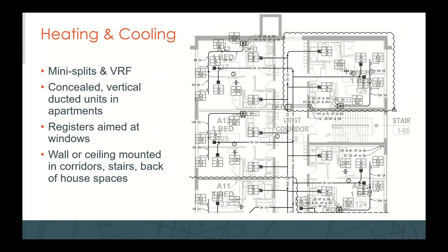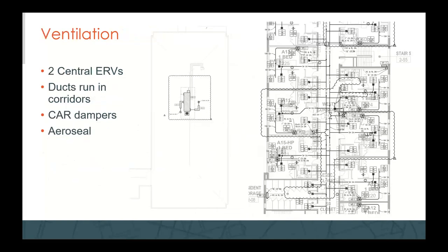Just some basic mechanical information here. As Christina mentioned, the building ended up upgrading its cooling with a centralized VRF scheme using vertical ducted units in the apartments, with registers aimed at the windows to wash them with conditioned air for comfort. Wall or ceiling mounted units were used in back of house spaces. For ventilation, ERV was always the plan, but a slightly more efficient unit was chosen to meet the passive house requirement. That's a picture of it on the roof.